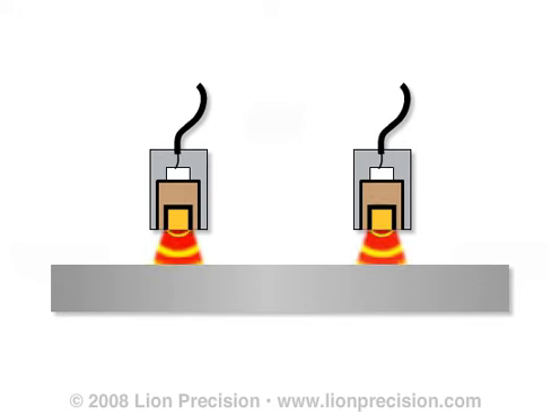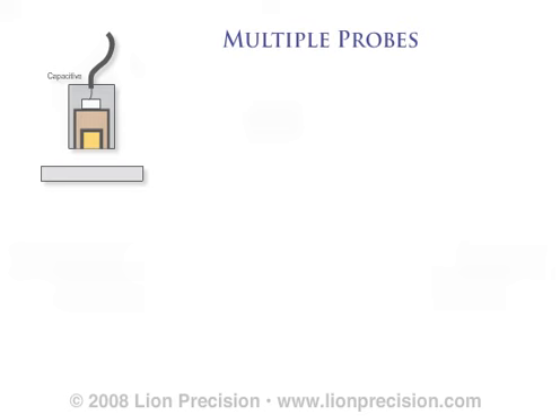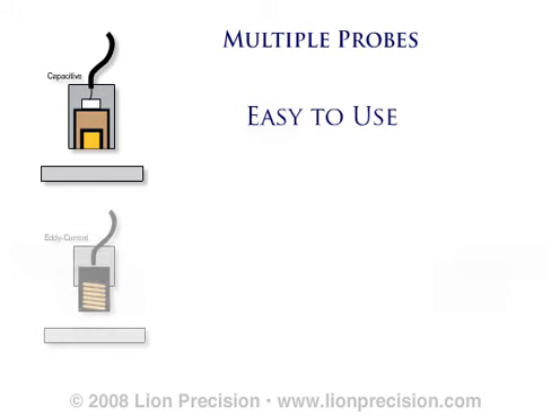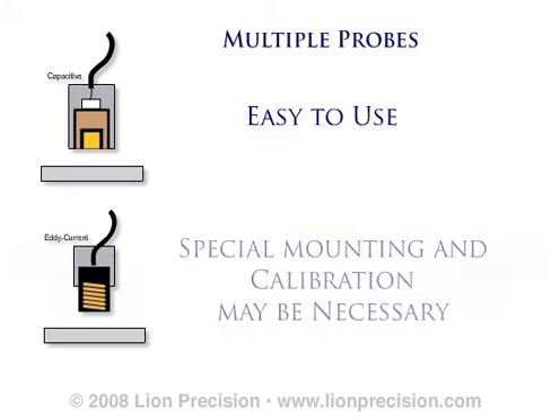Synchronization sets the drive signal of all sensors to the same phase so that all probes are adding or removing charge simultaneously and the interference is eliminated. All Lion Precision multiple channel systems are synchronized, eliminating any concern about this error source. When an application requires the use of multiple probes with a common target, synchronized capacitive sensors are very easy to use. If the application requires eddy current technology, special care must be taken in the mounting plan and special calibration may be required.